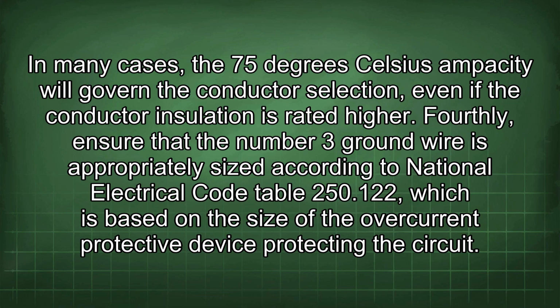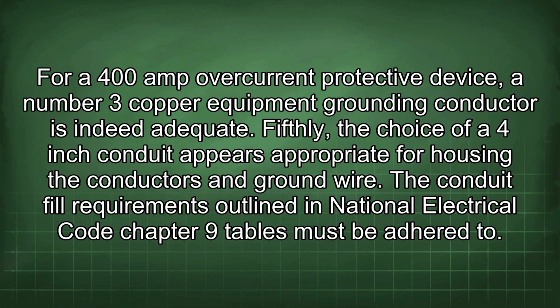Fourthly, ensure that the number 3 ground wire is appropriately sized according to National Electrical Code Table 250.122, which is based on the size of the overcurrent protective device protecting the circuit. For a 400 amp overcurrent protective device, a number 3 copper equipment grounding conductor is indeed adequate.